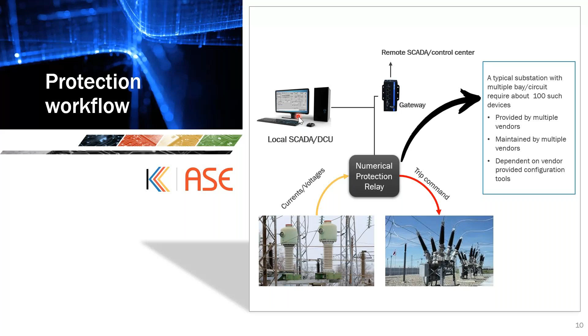So I'm just moving to an IEC 61850 based substation. Here we can see a similar workflow where we have the CTs and PTs in the field, which will sense the current and voltage. There will be an MU or a PIU that does the ADC conversion and provides the detailed data to the process bus. The data will be received by the multiple protection equipments, and each of these IEDs will be collecting the real-time samples from the process bus and running the protection algorithms inside the IEDs, and whenever there is a fault, they generate trips or corrective actions, which will be transmitted through GOOSE messages.